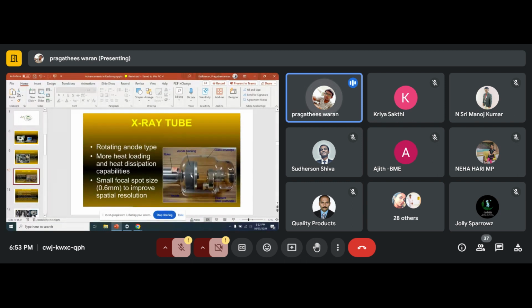If you are buying a tube, it is like buying a bulb: how do you rate it? In watts, I want a 100-watt bulb, I want a 60-watt bulb. With a tube, they say I need a 1.5 MHU tube, I need a 6.3 MHU tube, based on the slices. If they are using 64 slices or 128 slices, they will prefer high MHU tubes, so that the tube can withstand high heat dissipation.